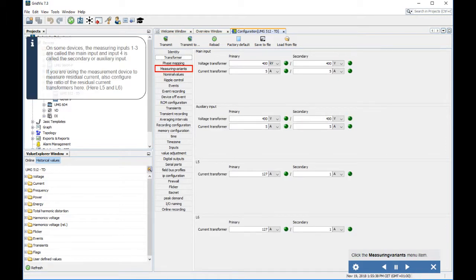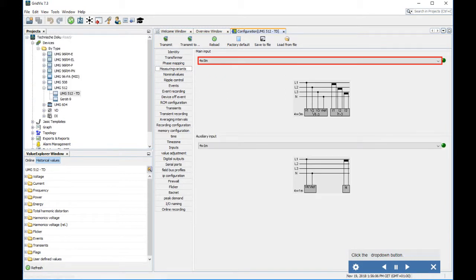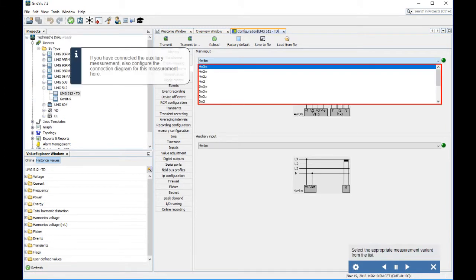On some devices, measuring inputs 1, 2, and 3 are called the main input, and input 4 is called the secondary or auxiliary input. If you are using the measurement device to measure residual current, also configure the ratio of the residual current transformers here — L5 and L6. Click the Measuring Variants menu item, then click the drop-down button.